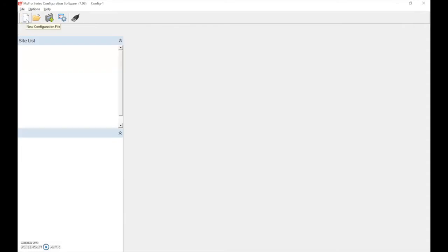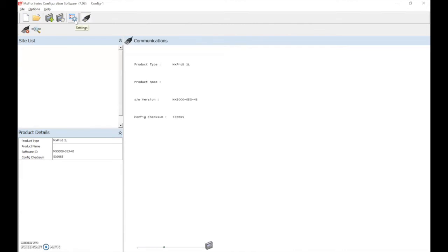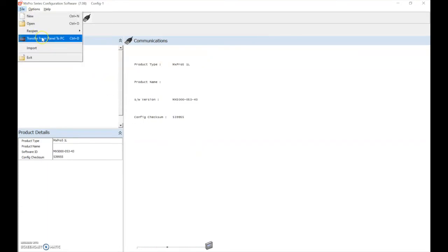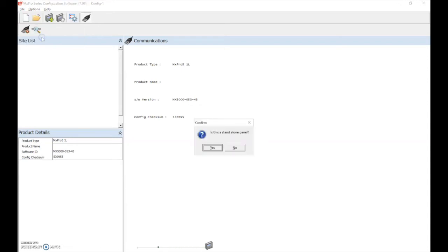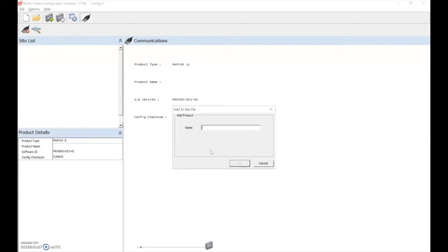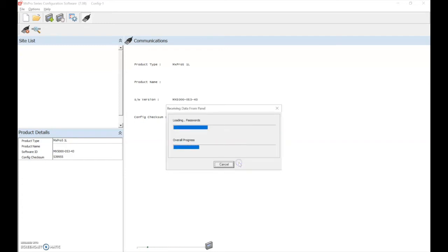To take the download, we first select the new file option, then select the communications icon. We achieve communications with the control panel, select File, and transfer from panel to PC. Confirm if it's a standalone panel and give the site a name. Once the transfer is complete, we select done.